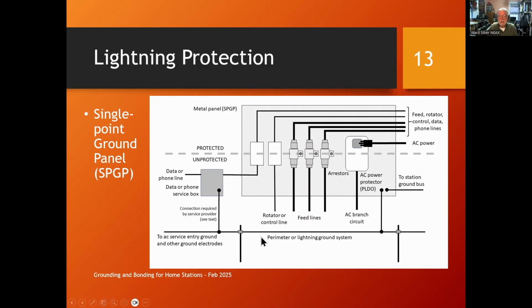So you basically tell them, hey, look, I got this nice perimeter ground system here. Please connect your ground terminal to that system. Okay. Now, you want to keep the protected and the unprotected cables apart. I know it looks a lot better if you have one big cable bundle with nice tie wraps and all this kind of stuff. You don't want to do that, because if lightning comes in on any one of these and it's bundled with these, it'll happily just jump from these to these and bypass your protection.